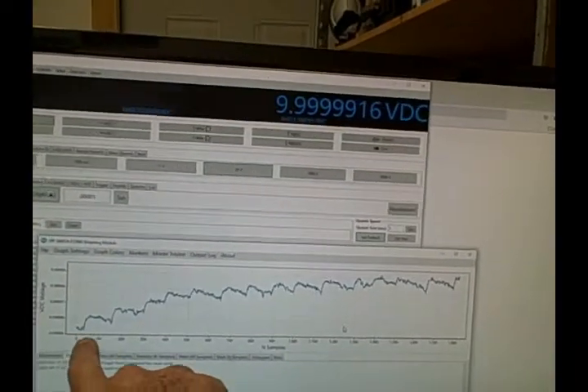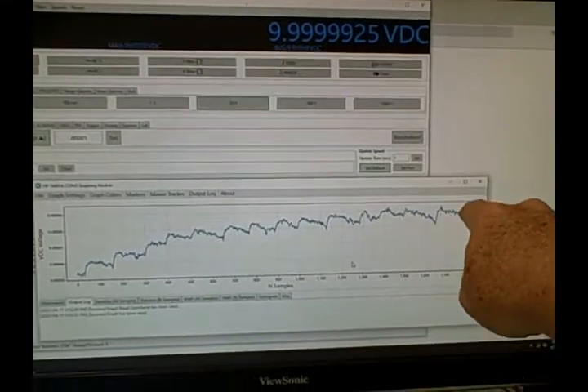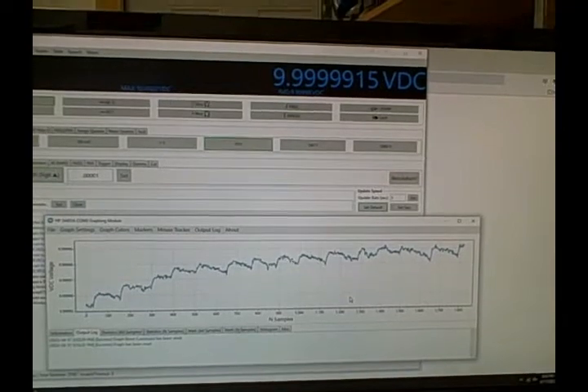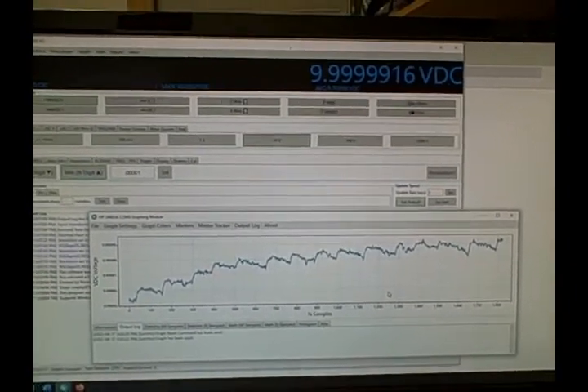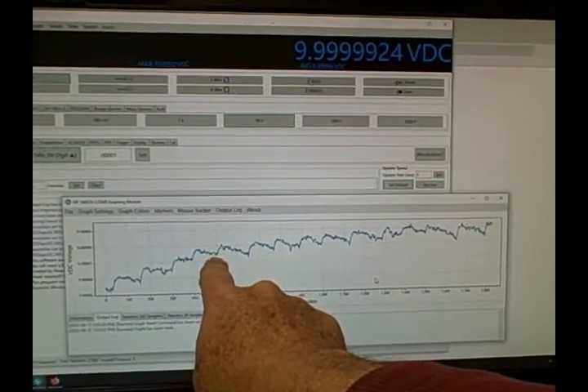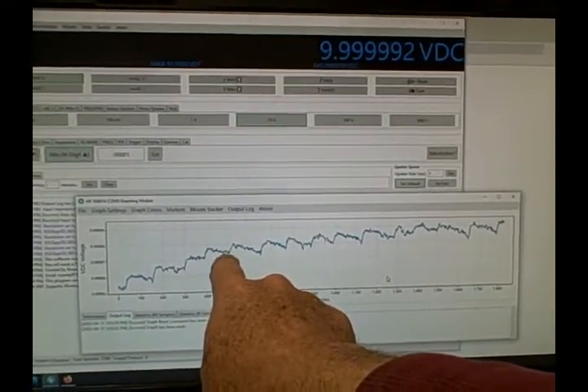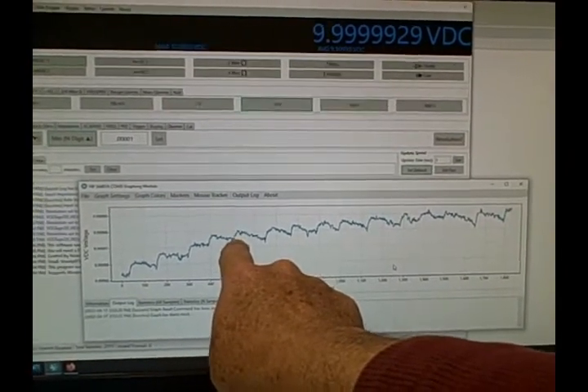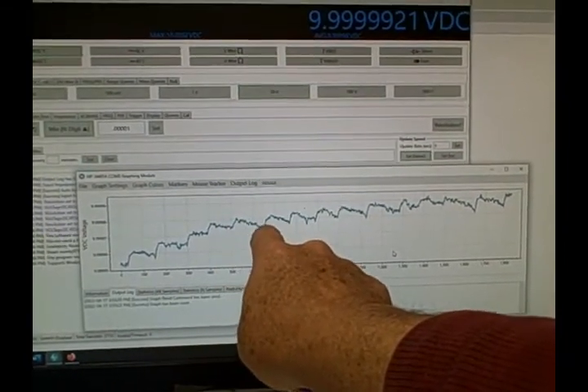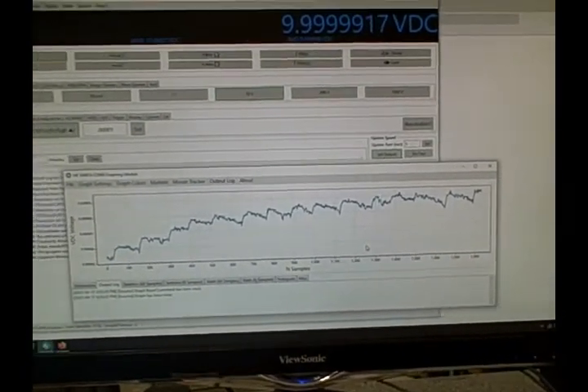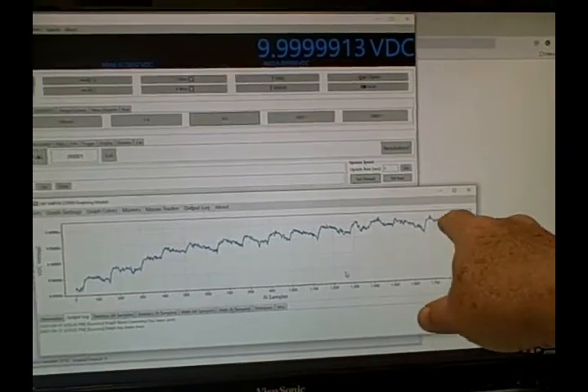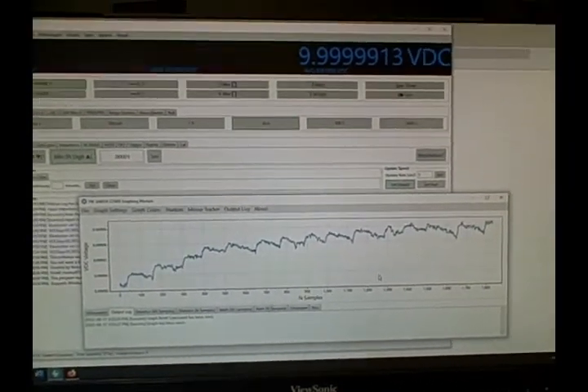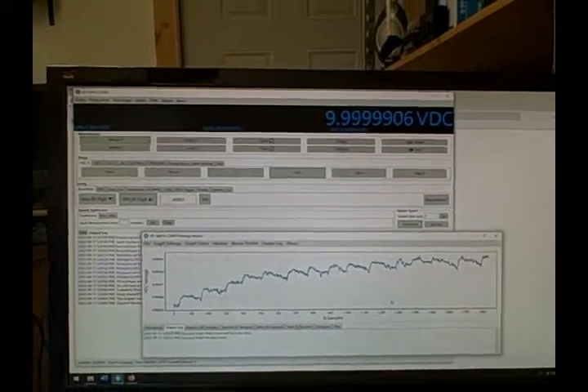So here we can see the effect of the warmup. That sort of logarithmic looking curve where we're approaching 10 volts. We are right now at 9.99999. So 9 point and then 5 nines. Approaching 10. And we can see in between the effect of the temperature control system, the heater that's inside. And we see that we basically go up approximately 5 microvolts. And then we drop down 5 microvolts and then up again and down. And it's periodic. Not absolute, but pretty consistent all the way up to the top. And once we finally level out, we should see that we maintain approximately 10 plus or minus 5. And we'll see what happens with that as we get there.